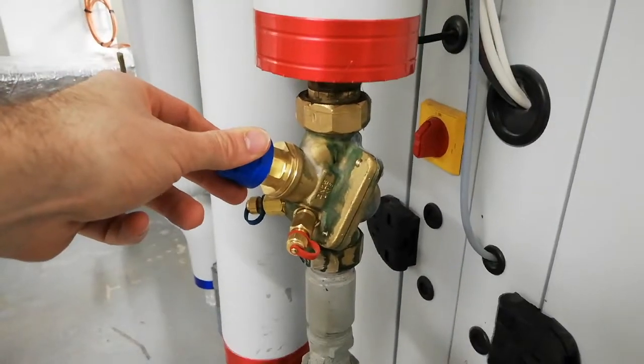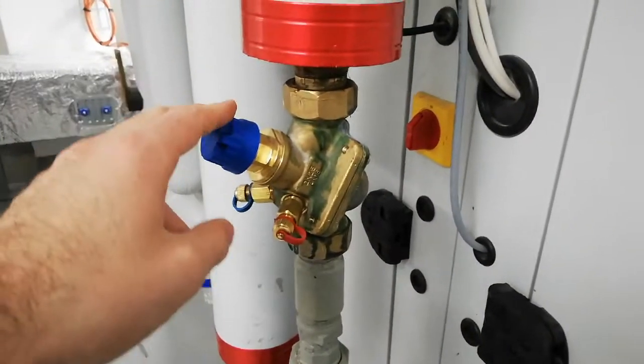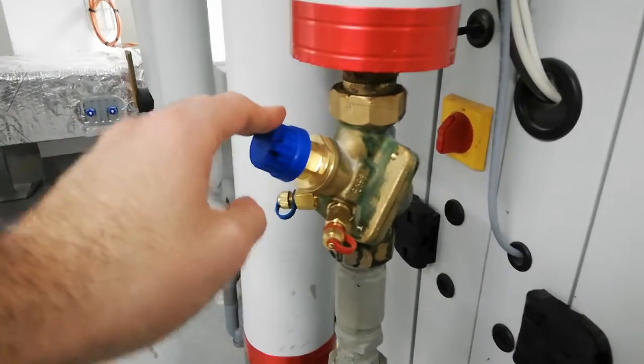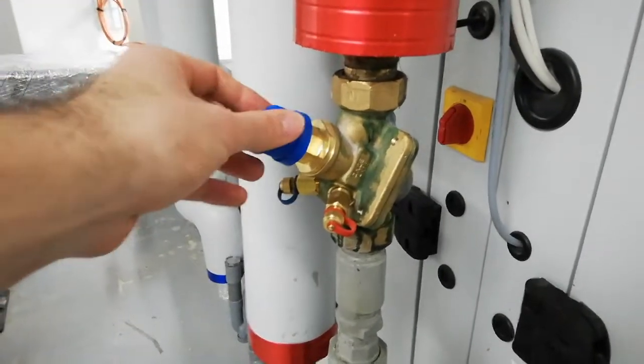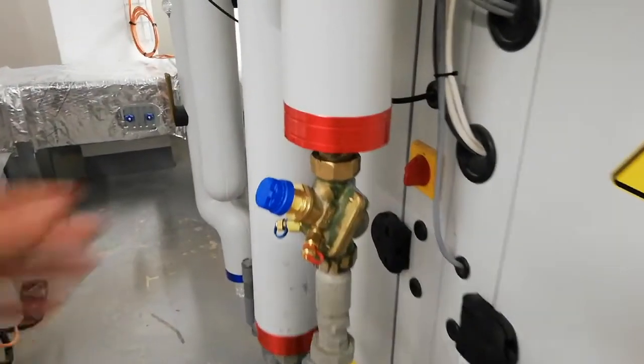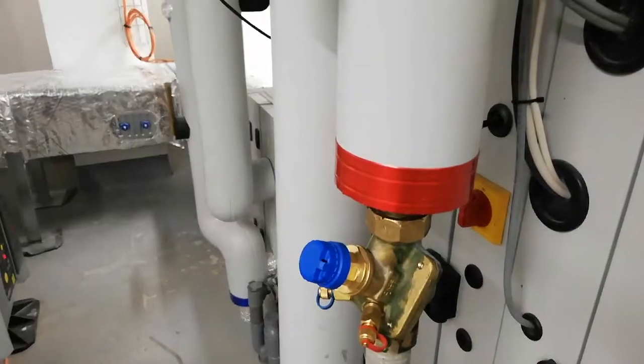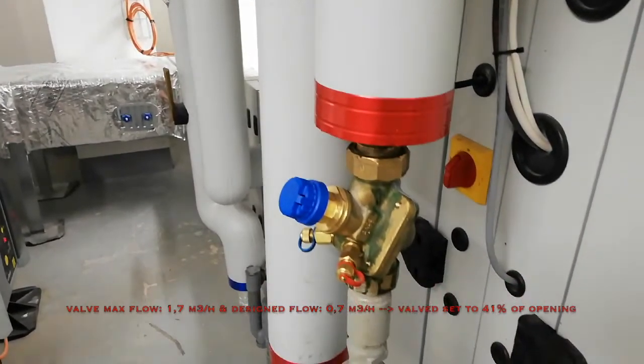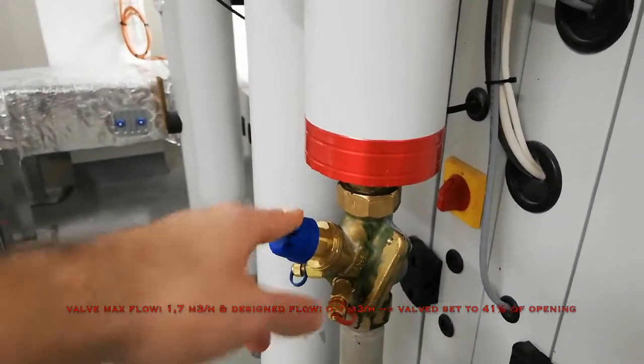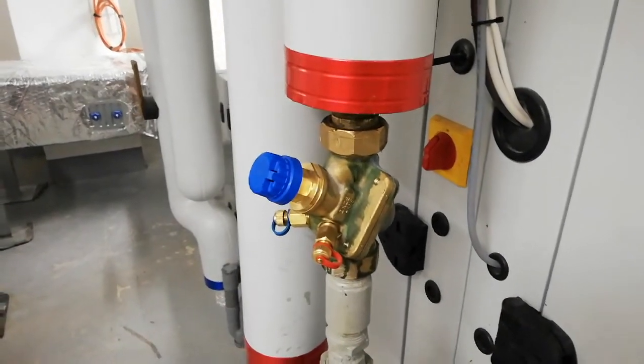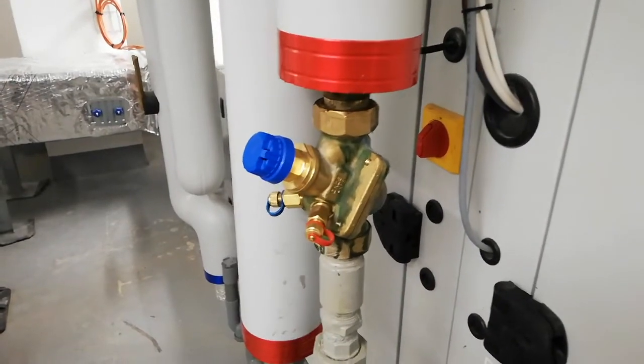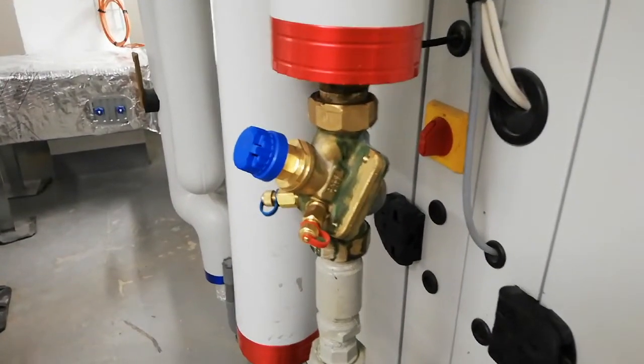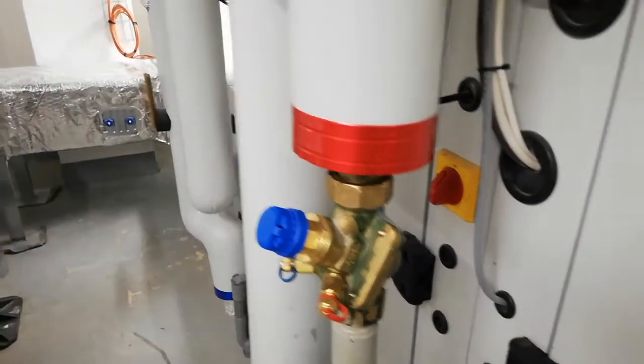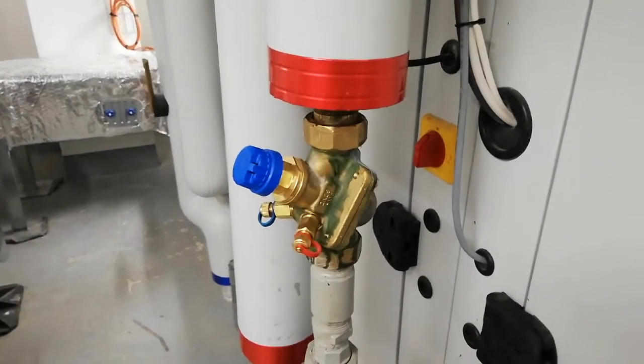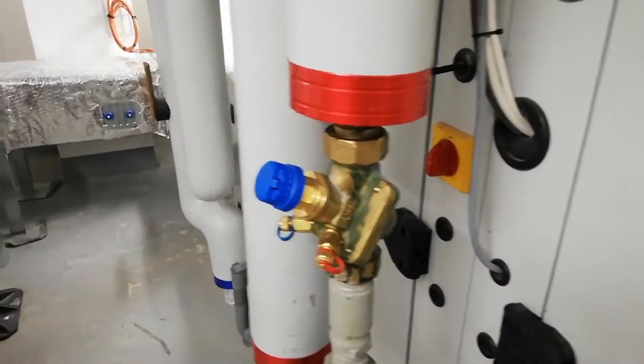There is close to zero commissioning for this type of component, because you just need to set the flow to the right flow during the installation. The maximum flow you can have in that valve is 1.7 cubic meters per hour, and the design flow for this one is 0.7. So you just need to set it to 41% of the maximum flow. And that's it. The installation is done. You won't have to do any balancing during the life of the building. This is what's really interesting in that valve, because you don't need to manually balance each valve every time you add a new coil or a new terminal to your system.